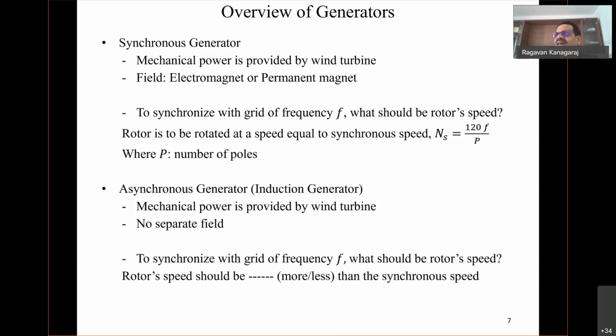If you are connecting this generator to the grid, and the grid is maintained at a certain frequency, the shaft of the generator should be driven at the same speed so that you get the frequency matching that of the grid. We are not directly connecting, we are putting a gear system, so after the gear ratio, you need to know what speed the shaft of the generator will see. The number of poles are then decided accordingly, so that the frequency from the generator matches the grid requirement. Now another generator is the asynchronous generator.